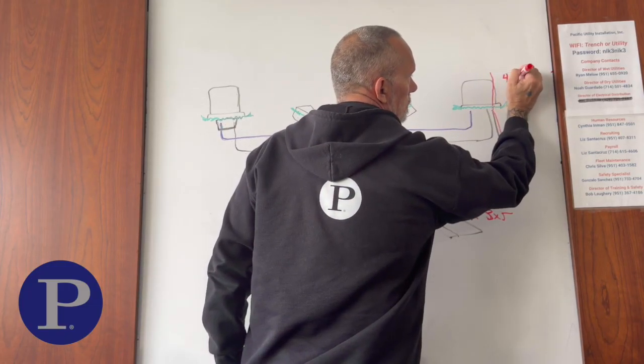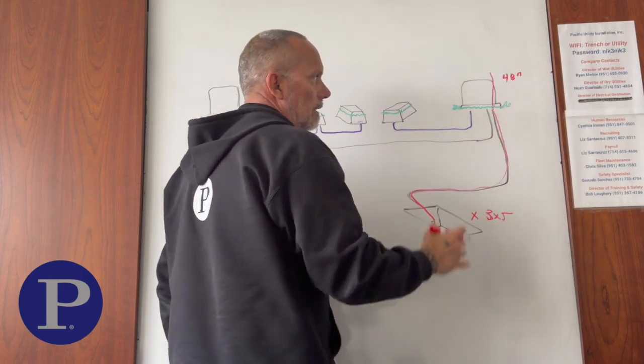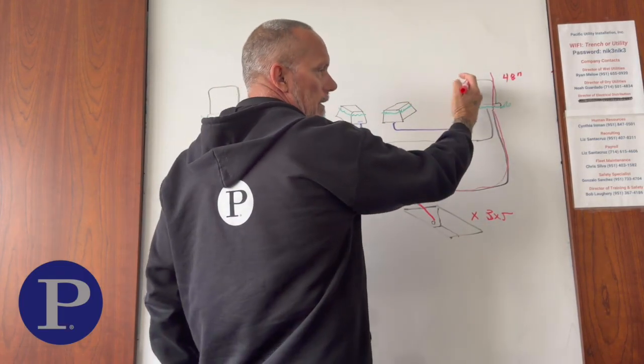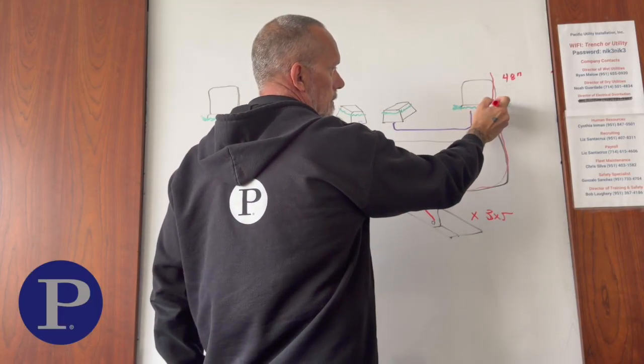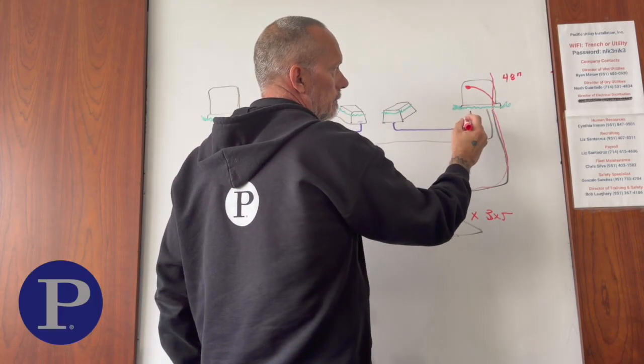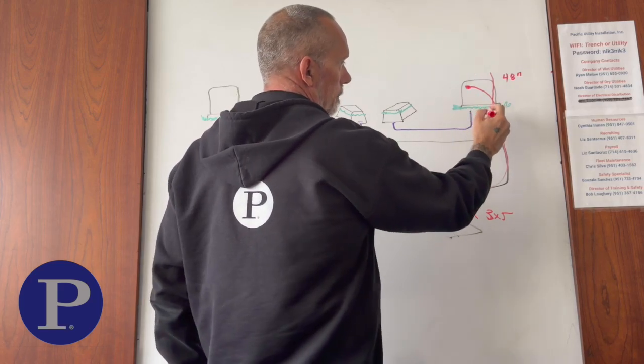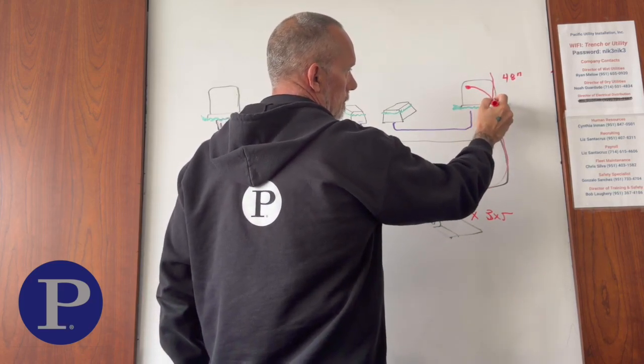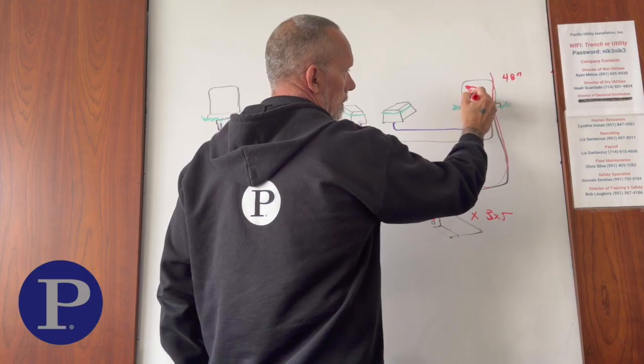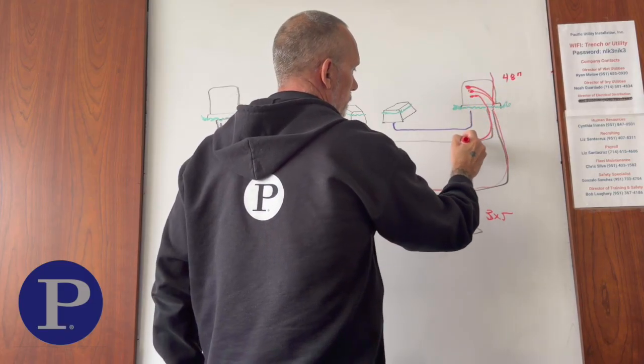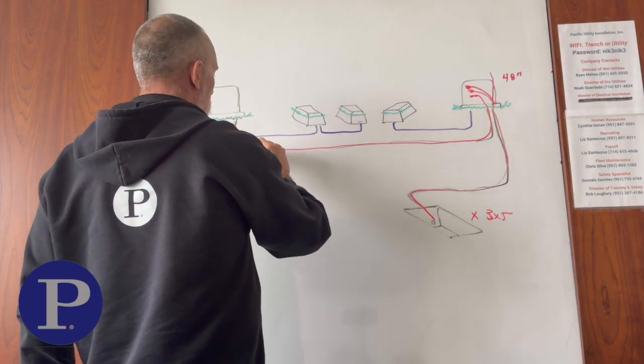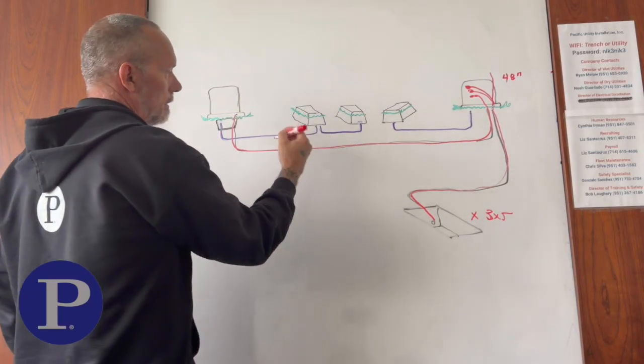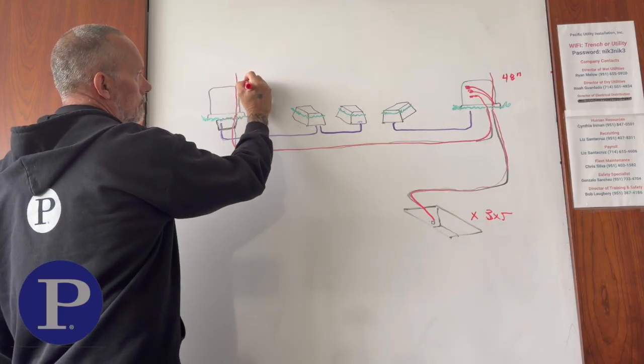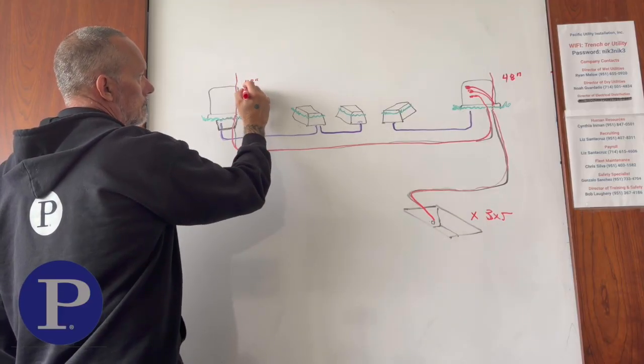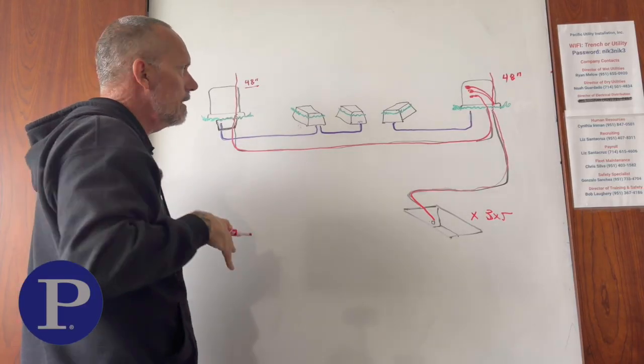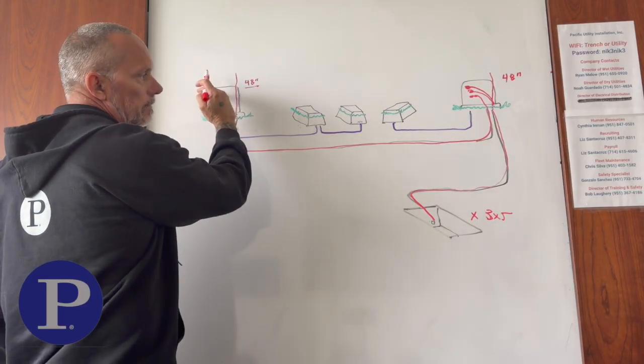about 48 inches above the pad. That gives you enough room to play with the cable, get it laid in once we're doing the splicing and stuff like that, because this is going to come over here and it's going to land on a bushing over here. From there, it's also going to exit. You'll have two cables coming in here and then two more going out. From the transformer, it's going to go all the way into the next transformer. And again, this is going to come up 48 inches, approximately where you're going to cut it, about chest height. That'll give you enough room to lay it over and make your cuts.